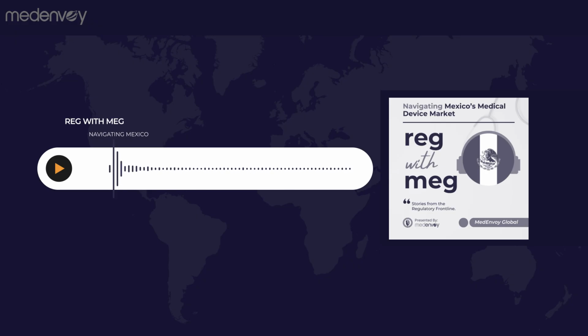And what about labeling? We know that's always a major point of inspection. A critical one. All labeling, and that includes the packaging, the device label itself, and any instructions for use, must be in Spanish. It must also comply with specific Mexican official standards, known as NOMs. The NOMs dictate exactly what information must be present, like the registration number, the MRH details, and country of origin. This has to be correct before you ship, not something you try to fix at the border. It sounds like having a really good customs broker and a licensed importer is non-negotiable. Absolutely essential. You need partners on the ground who specialize in medical devices.